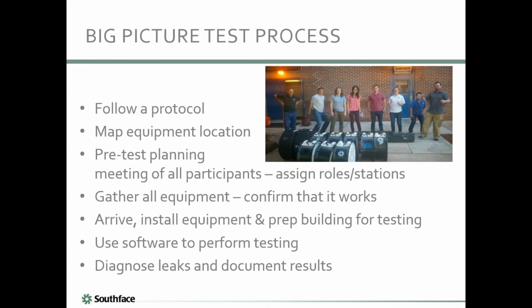So here we are, Burke. I think this is a 1929 school we were testing. No, it looks like we got about 10 fans and a pretty big crew out there. I remember we had 10 fans, and it still wasn't enough to get to the test pressure. But after our improvements on this particular one, it was more than enough. I remember we did some impressive air sealing. And so we've learned some stuff from getting out there and doing these tests. Yes, we have.